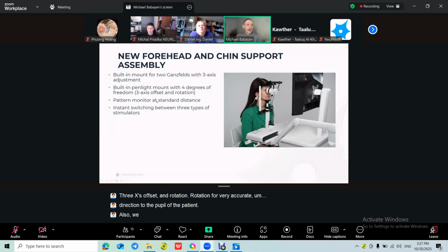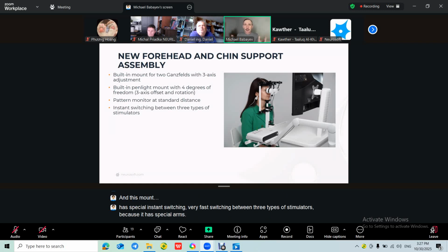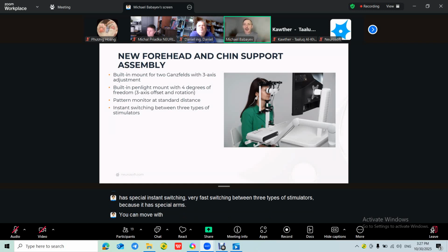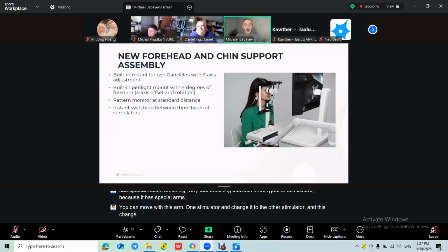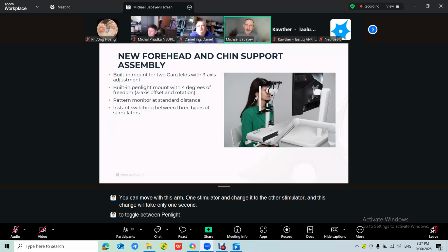Also, we have here a pattern monitor at a standard distance of 30 centimeters. And this mount has special instant switching, very fast switching between 3 types of stimulator because it has special arms. You can move one stimulator with this arm and change it to the other stimulator. And this change will take only 1 second to toggle between the pen light, Ganzfeld stimulator, and pattern stimulator.